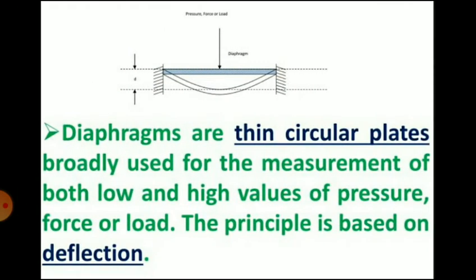Then second is the diaphragm pressure gauge. Diaphragms are thin circular plates broadly used for the measurement of both low and high values of pressure, force or load. The principle is based on deflection. When there is a difference in pressure between the two sides, then the center of the diaphragm becomes displaced. Corrugations in a diaphragm result in a greater sensitivity. This movement can be monitored by some form of displacement sensor, that is a strain gauge.